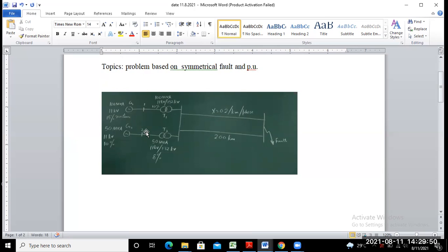Now what was the second step? Second step is your find the per unit reactance of all the component involved in power system based on 1 base MVA and base kilovolt. Is it not? Whatever the component involved in power system, we try to find out per unit reactance value on the same base value or one base common base value, common voltage and MVA rating. Okay.